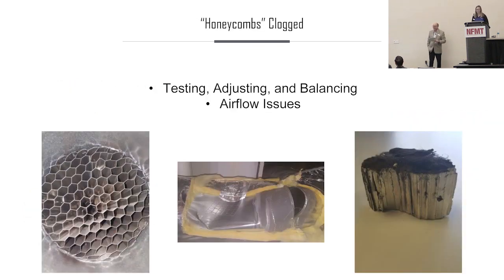Honeycombs. They've got a good intent. However, if they're not clean, they end up being an obstruction in the ductwork. So if you have an existing building and there are honeycombs there, try to add access panels. And if you have a new building where they're installing them, try to advocate for access panels there, because we've been in buildings where they're like, yeah, there's a honeycomb, but we had to cut the ductwork and then weld it back together to clean the thing.